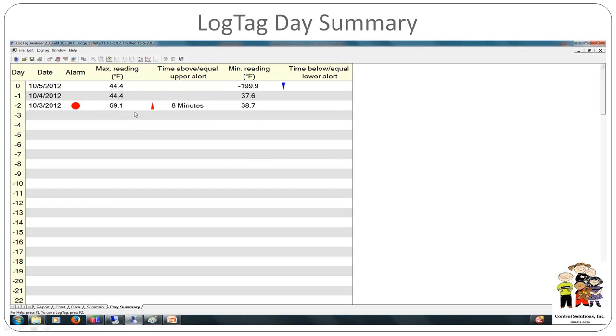If you're doing your morning inspection or just need to check your min-max for the week, this day summary is the page to go to. Notice that on the second day I was at 44.4, and on the last day these numbers are almost identical, because most refrigeration units should have a repeatable control offset. You can also notice that on the last day, as I demonstrated earlier, I had the sensing wire unplugged and it went to minus 199.9 degrees.